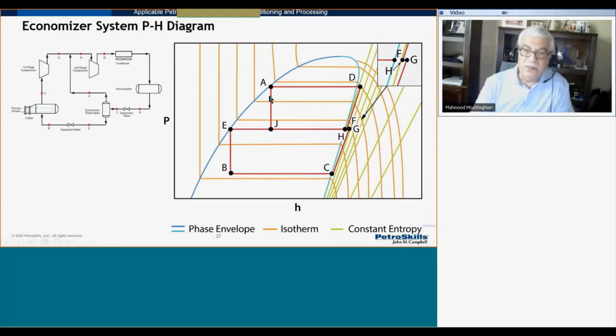So what we have, we add one additional expansion valve. Originally we had an expansion valve upstream of the chiller, still we have it. So we add this expansion valve, a separator, additional separator, plus one more stage of compression.